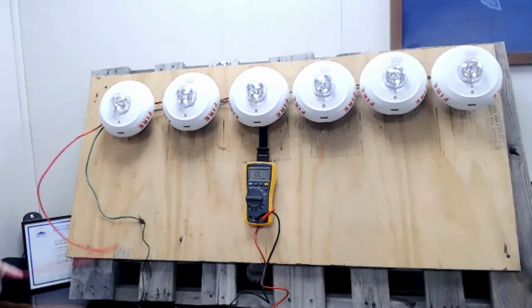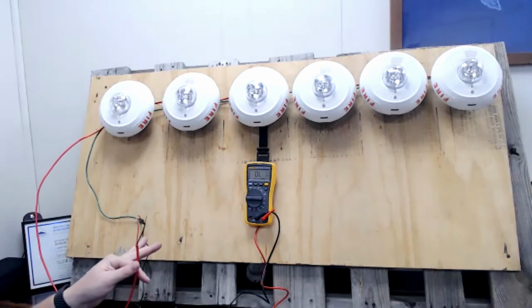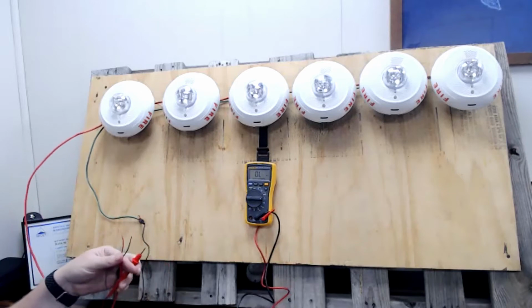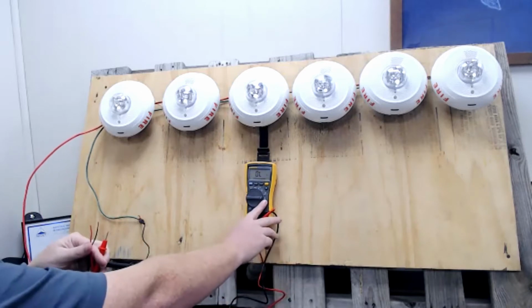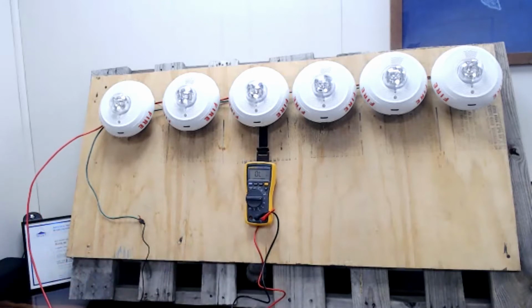So the first thing we want to do, say we have our circuit completely trimmed out, completely built, ready to land on a panel, and we have our home run here, and we're ready to land this home run to its terminals. Before we ever do that, we want to take our meter leads and have it on that omega ohm setting because we want to check for resistance. We need to look and make sure our whole circuit's there.